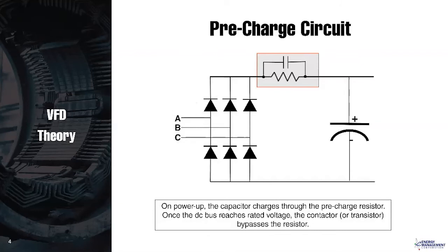The next slide is going to bring in our inverter. Oh, I'm sorry, I got one slide ahead of myself. This is the soft charge circuit. So soft charge circuits can vary somewhat, but this particular one has a resistor and a contactor. When you first energize the drive, if you don't have that in there, it will basically be a short circuit between the power system and that capacitor. Electrolytic capacitors don't like that. They tend to blow up, and we tend to think that VFD blowing up is a bad thing. And so all manufacturers that I know of low voltage drives include a pre-charge or a soft charge circuit. So when you first energize the drive, the capacitor fills through that resistor, which limits the amount of current going into that capacitor. It also prevents fuses from blowing and breakers from tripping and so on.